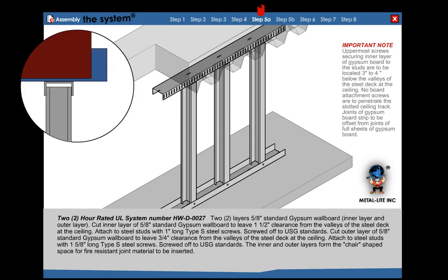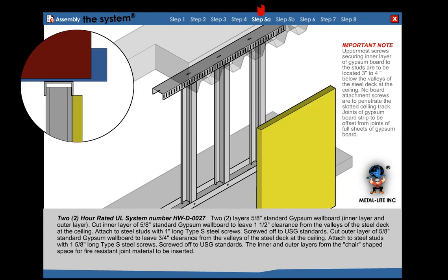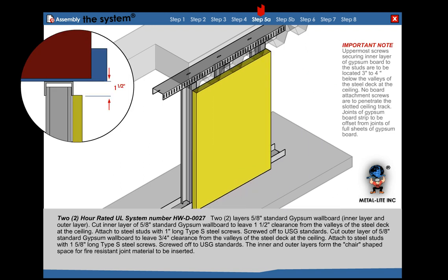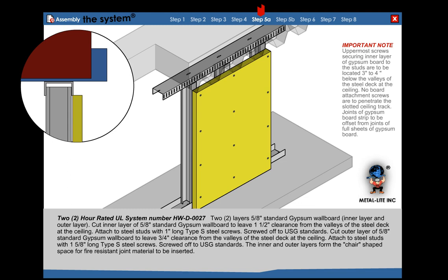Step 5a: For a 2-hour rated system, use two layers of 5/8 inch gypsum wallboard. Cut inner layer 1-1/2 inches short of the valley of the fluted deck. Attach to steel stud with 1 inch Type S steel screws, screwed off to USG standards.